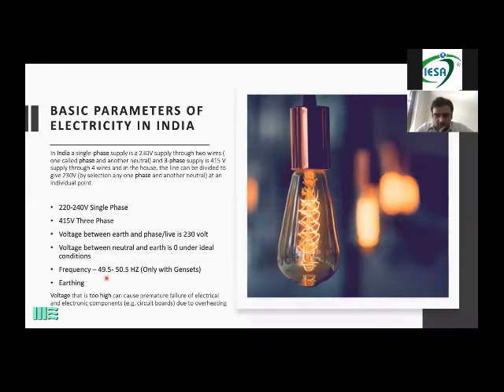Frequency is valid for your gensets. The frequency has to be set between 49.5 and 50.5. What is frequency? It is just the running cycles of the gensets. So frequency always has to be within this range. If all these parameters are right, you can switch on your electricity.